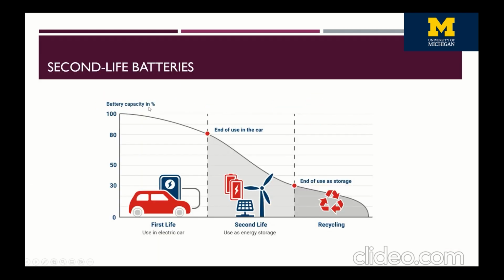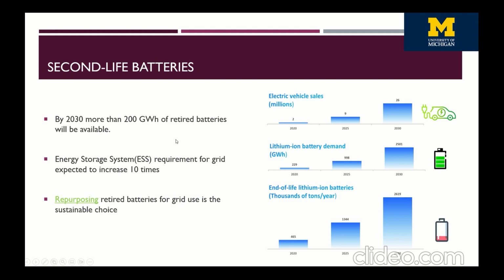The main idea is to use retired batteries from electrical vehicles in the electrical grid. We know that EV batteries after a certain amount of use are retired. Most EV manufacturers recommend retiring batteries when capacity reaches 80%. At 80%, the battery still has enough juice left, although it's not suitable for EVs anymore, but it can be put to second life use, most appropriately as energy storage for the electrical grid, usable down to around 30%. After that, the battery can be totally retired and recycled for rare earth minerals like lithium, cobalt, and manganese. So why should we use batteries for a second life?